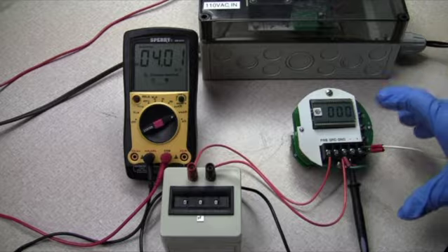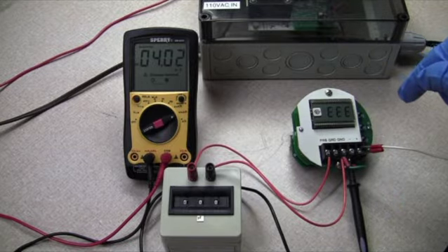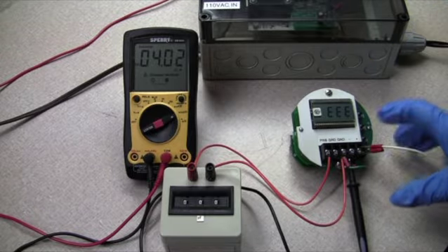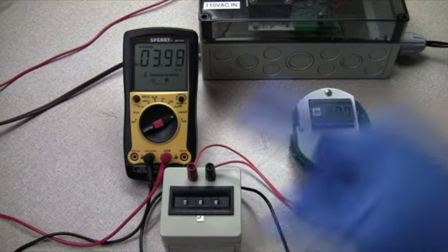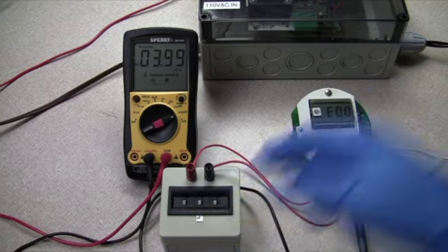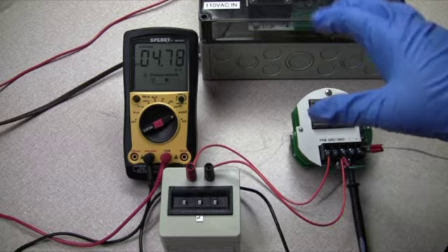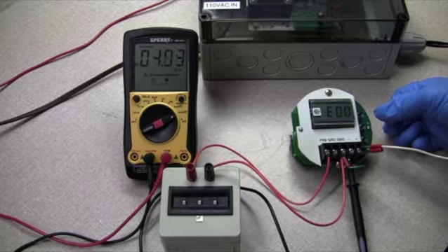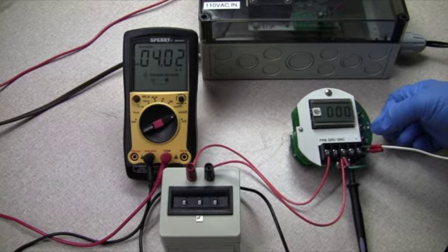Setting your low is simple. You hit the SW2 button to enter the low set point. E will display for empty. Hit the SW3 button, and now you can set your low set point. Right now I have it at 0, 0, 0. I can go up with it. This is simulating the percentage of tank full. But we want to be at 0 when we're at 4 milliamps. So we go to E00, hit the enter SW3 key, done.